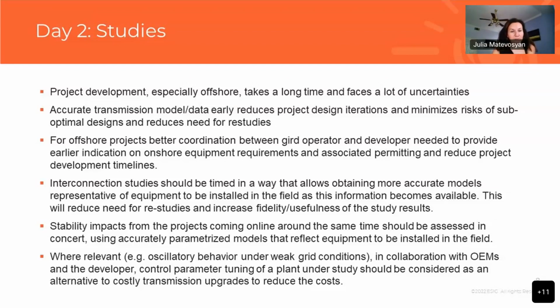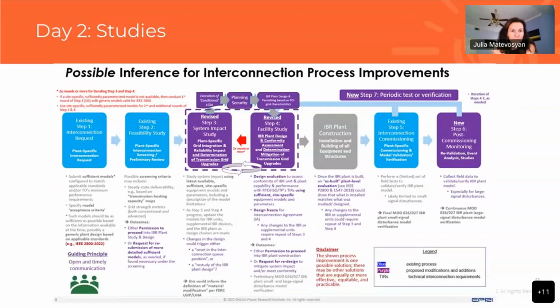And where relevant, for example, oscillatory behavior is being seen under weak grid conditions. In collaboration with OEMs and developers, control parameter tuning can be used as an alternative to transmission upgrades to save costs. And so we heard from Alice Shatak from Vestas talking about one of those cases where an expensive transmission upgrade was avoided just by tuning control parameters at one plant. But this also can be done in a number of plants that are, say, coming in together in the same area, or there are existing inverter-based resources and new resources are coming. And so control parameter tuning is very helpful there.